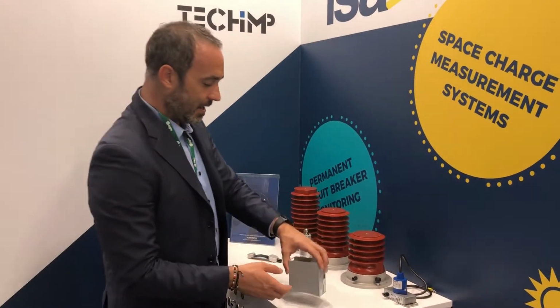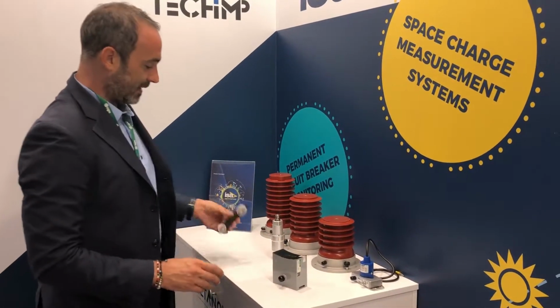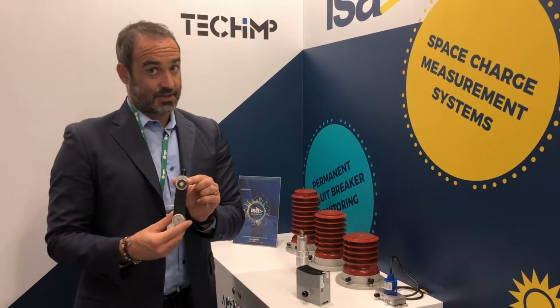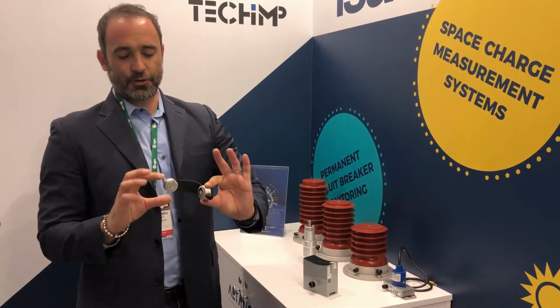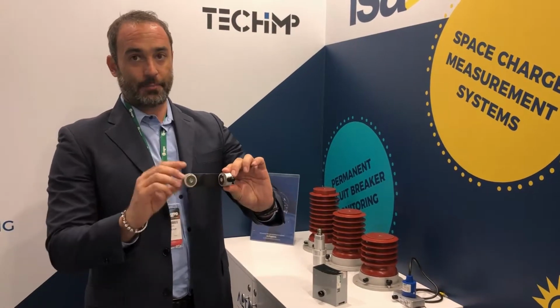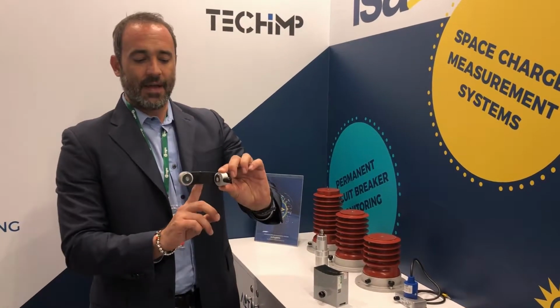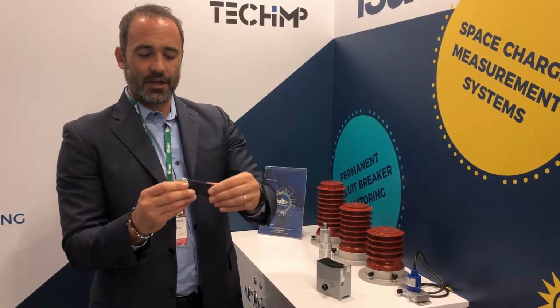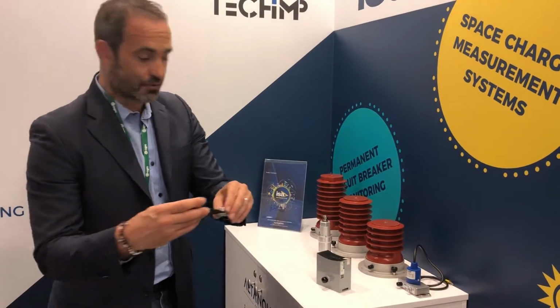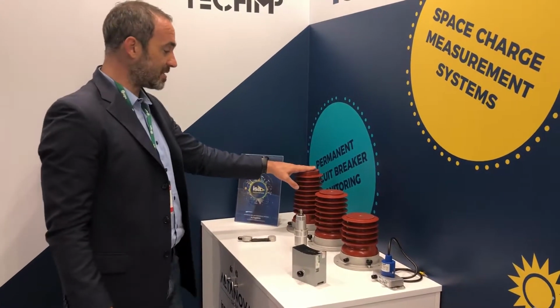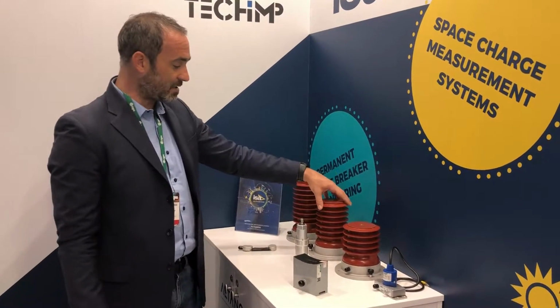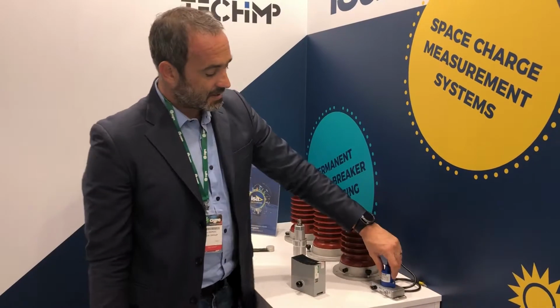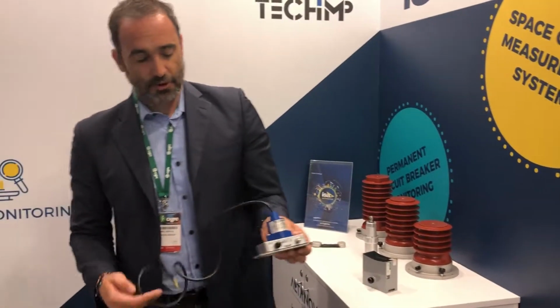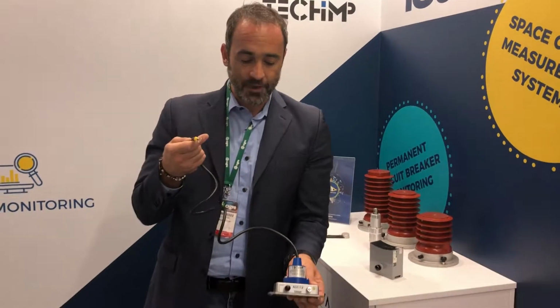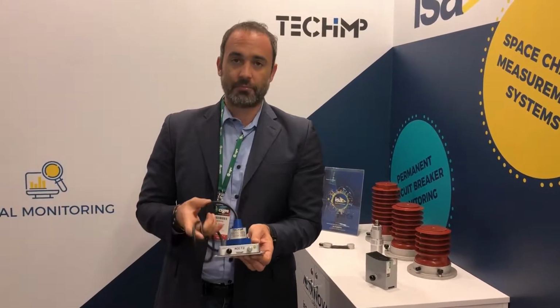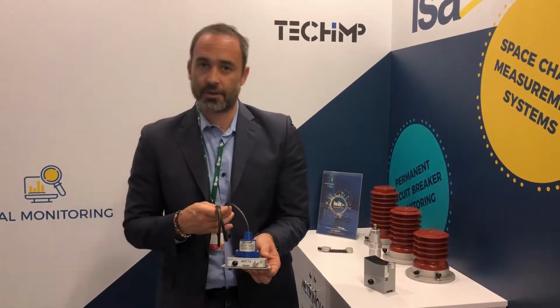Apart from our UHF antenna, we also have the TEV sensor used on medium voltage switchgear. These are two magnets which you need to place and have an air gap in between, so on the doors or between maybe two cubicles. And you also have the sensor inside here in order to sense the PD which you're trying to measure. Last but not least, we have sensors, capacitive couplers for rotary machines, 24, 17.5, 12 and 7.2 kilovolts. This is the latest product coming from Techimp R&D. Very useful and very good to install on medium voltage motors or maybe even some smaller generators.